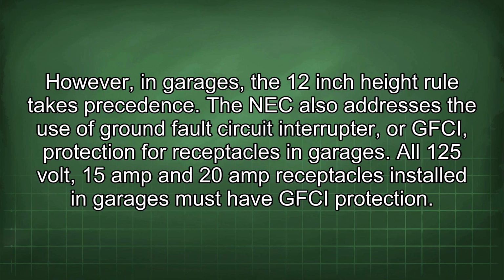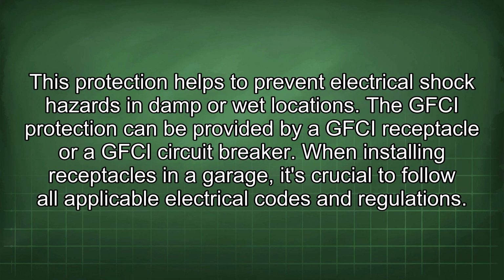The NEC also addresses the use of ground fault circuit interrupter, or GFCI, protection for receptacles in garages. All 125-volt, 15-amp and 20-amp receptacles installed in garages must have GFCI protection. This protection helps to prevent electrical shock hazards in damp or wet locations. The GFCI protection can be provided by a GFCI receptacle or a GFCI circuit breaker.